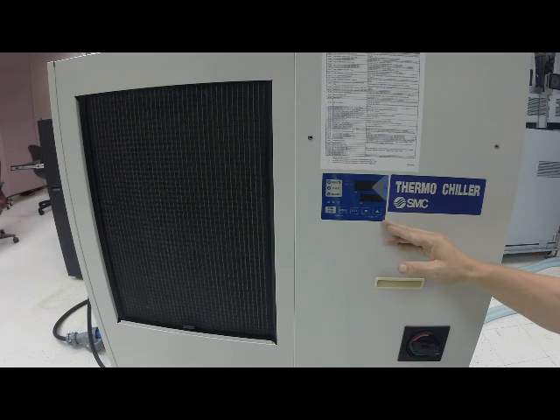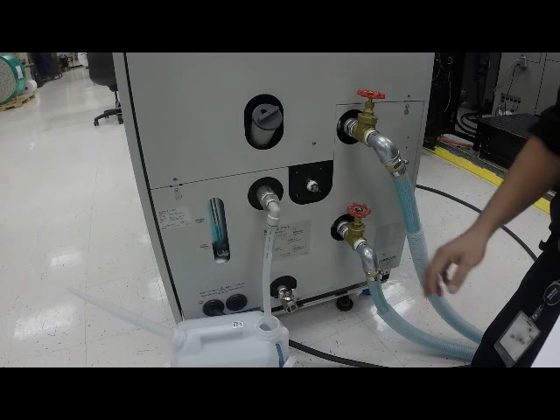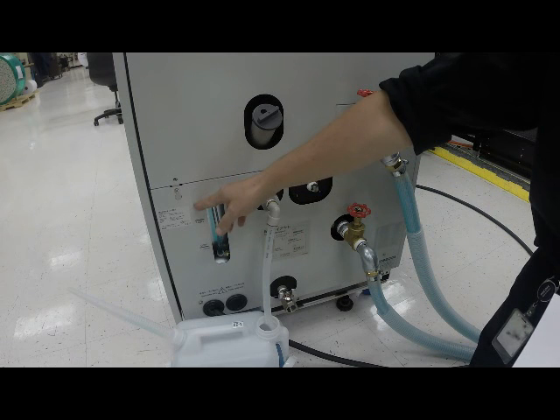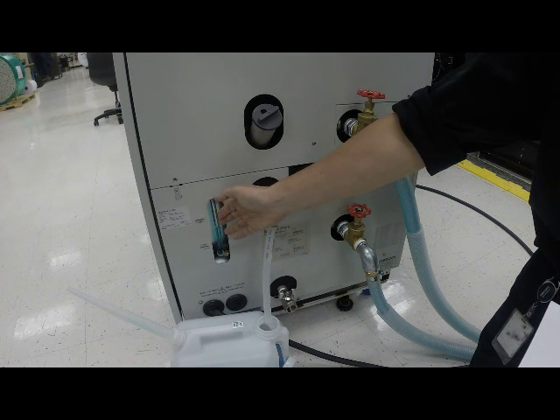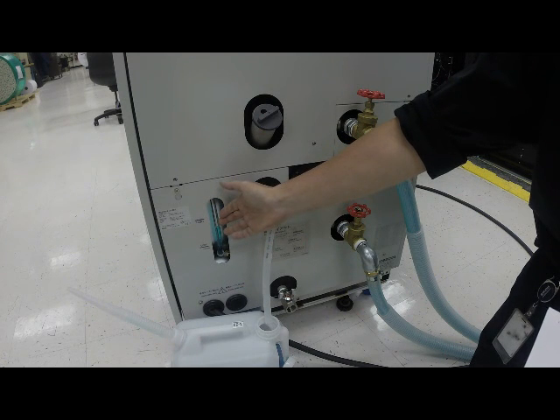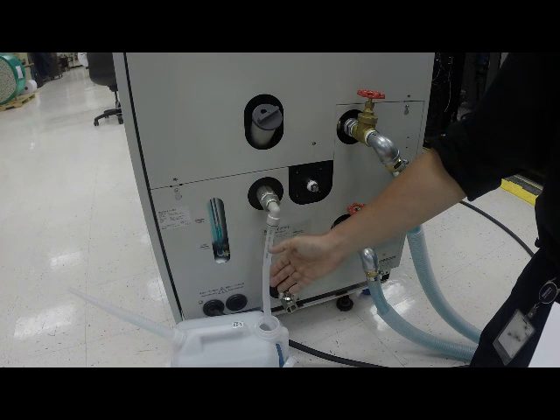The operation display panel is your main control panel for operators and technicians. On the right side of the chiller, you will find the product label, which has the SMC model number and serial number. Next to that is the fluid level gauge. You can see that our fluid is right between the high and low mark. The overflow port is used mainly for customers who have an automatic fill port hooked to the customer's water supply. Our systems should not have a problem with overfilling.